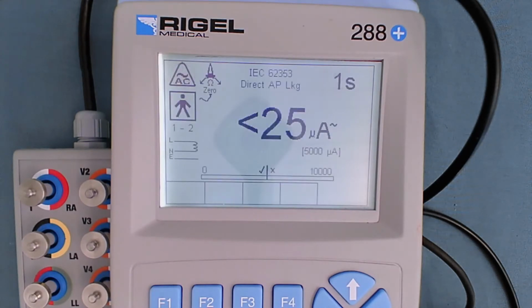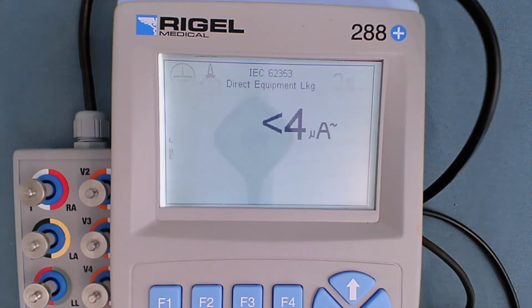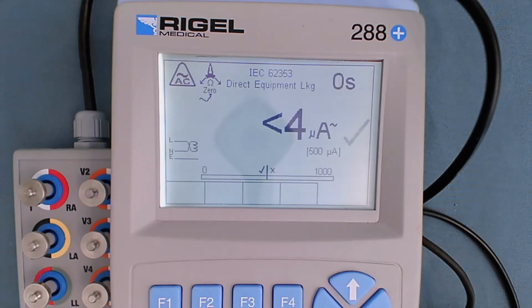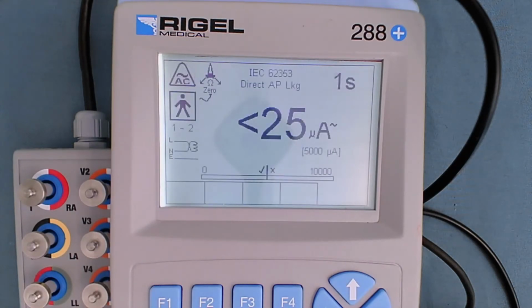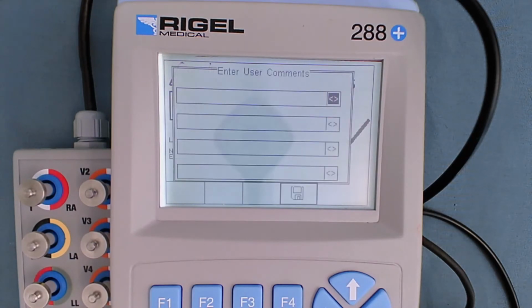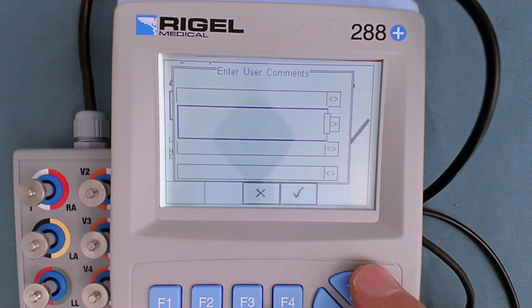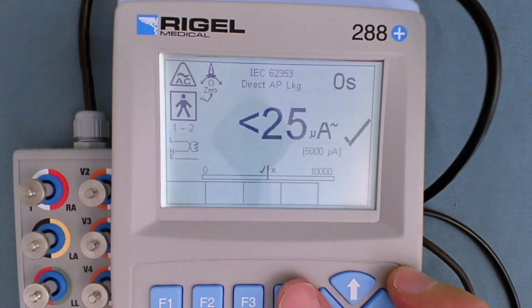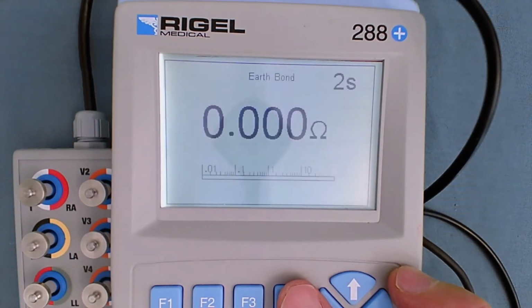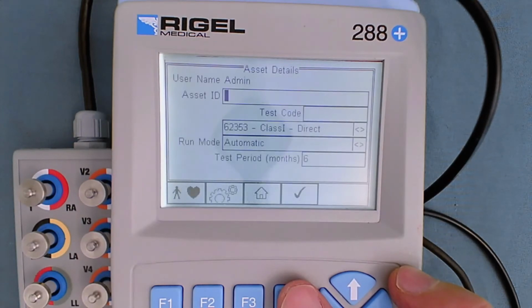So there's no applied parts connected. The values are going to be lower than the resolution of the instrument, obviously, but it's going to be below the range, and there's no applied parts connected for this test. Okay, so when you get to this screen, you can enter any user comments. Let's say that's passed. And that's an automatic test. Now that's automatically stored under that asset ID.